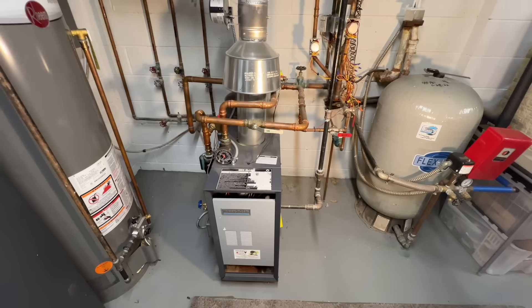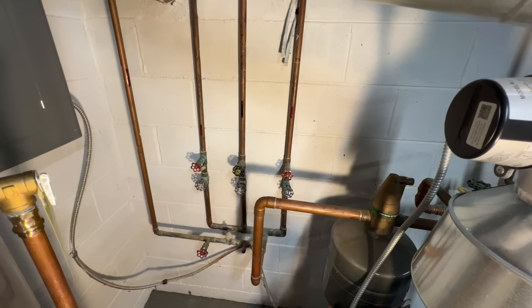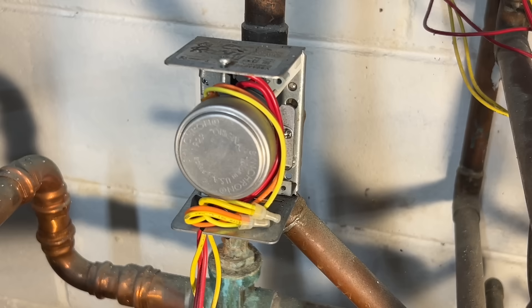If you're not familiar with it, this is a boiler system. This box in the center is actually the boiler — it heats up the water and then pumps it through a bunch of different pipes through valves. Each room has its own set of pipes. The water runs through the pipes into the room and then comes back, and that's how it heats the room. It's controlled by valves, and this is one of the valves — in fact, this is the one that's sticking.